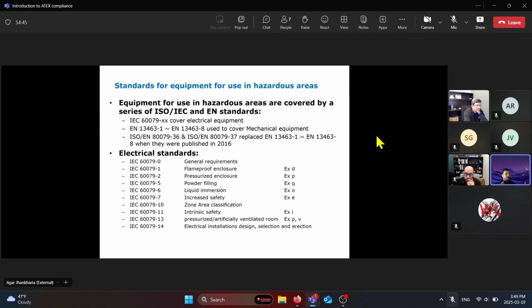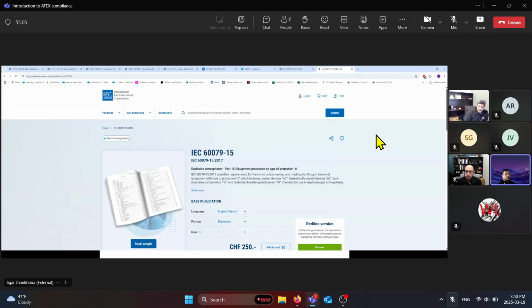In the past, it used to be called IEC 60079-15, and I can pull that up here. I believe it was for non-arcing, for non-sparking, if I'm not wrong. Yeah, protection of type N. So basically they changed this to 60079-7 for increased safety. The standard is still valid, but it only applies to hermetically sealed devices. So it doesn't apply to non-incendive components anymore. That's been updated in the standard.